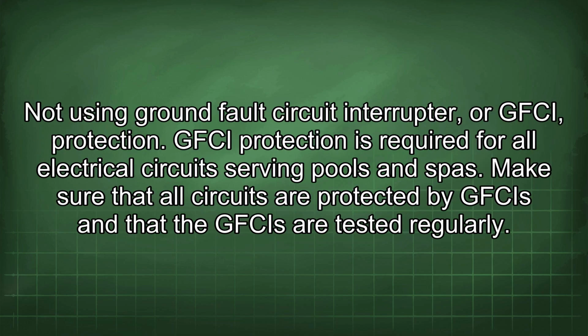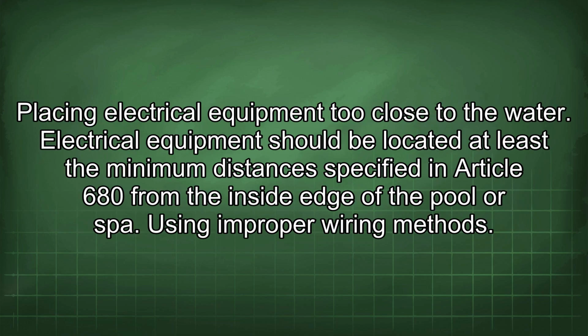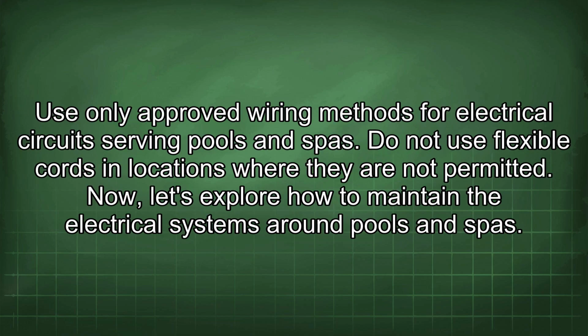Not using ground fault circuit interrupter or GFCI protection. GFCI protection is required for all electrical circuits serving pools and spas. Make sure that all circuits are protected by GFCIs and that the GFCIs are tested regularly. Placing electrical equipment too close to the water. Electrical equipment should be located at least the minimum distances specified in Article 680 from the inside edge of the pool or spa. Using improper wiring methods. Use only approved wiring methods for electrical circuits serving pools and spas. Do not use flexible cords in locations where they are not permitted.